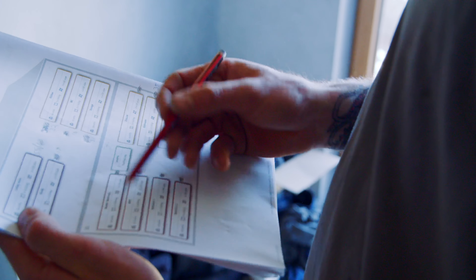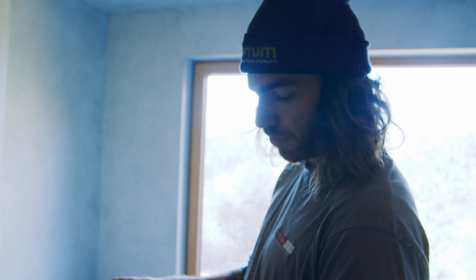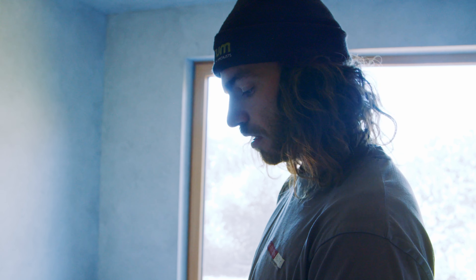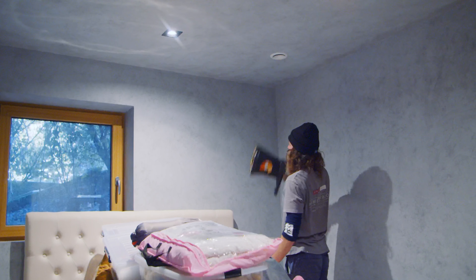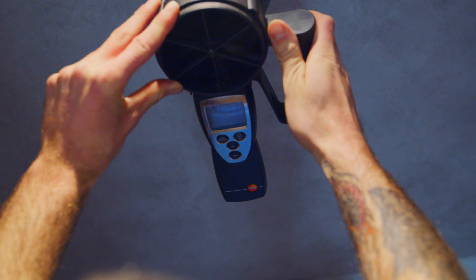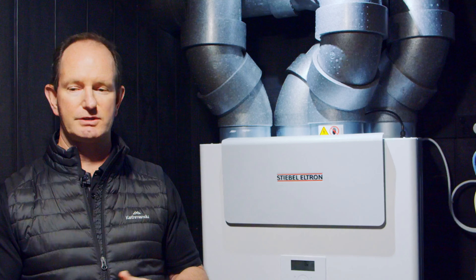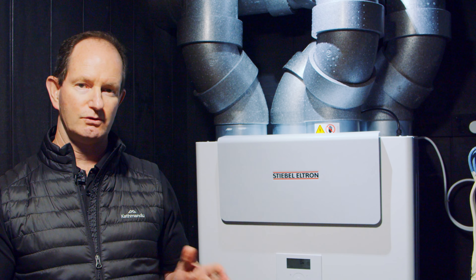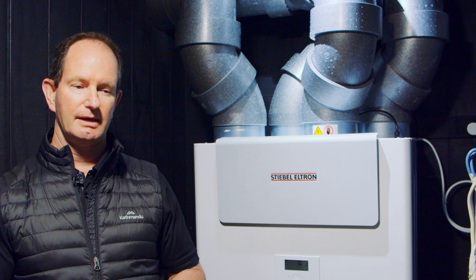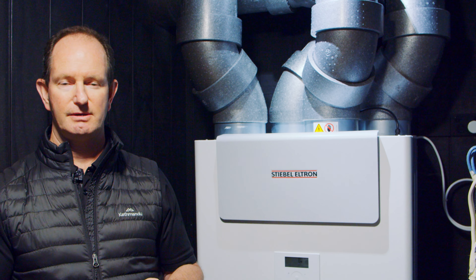I'm commissioning this MVHR unit, going around and measuring the air speeds — getting an average reading of what's coming out of every single extract and intake. I'm going to read in on the master bedroom over here. Master bedroom came through at 16 on my reading, and according to Stiebel Eltron, I'm looking to achieve 30. We'll carry this out across the whole house, getting the readings of what we have now, and then adjust each dropper to achieve the right reading.